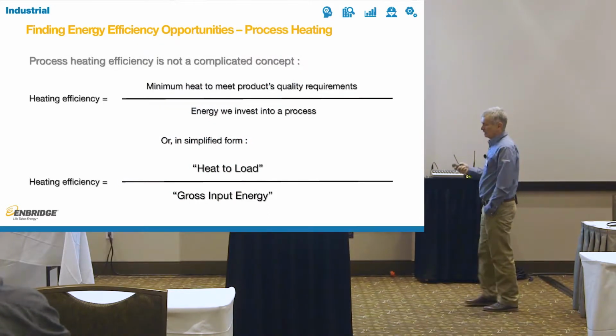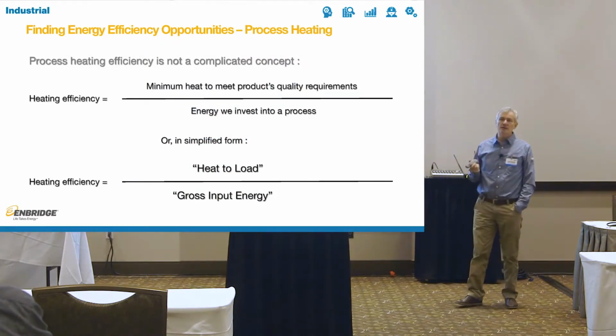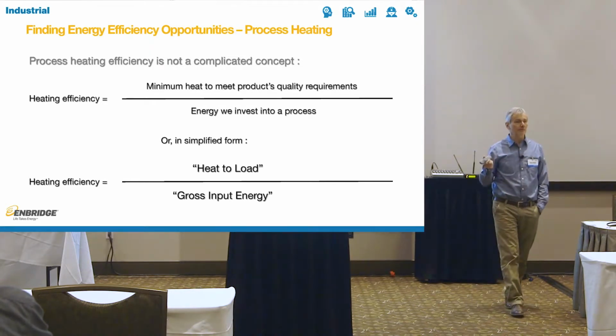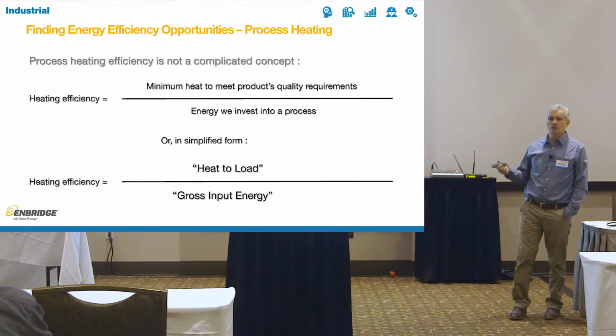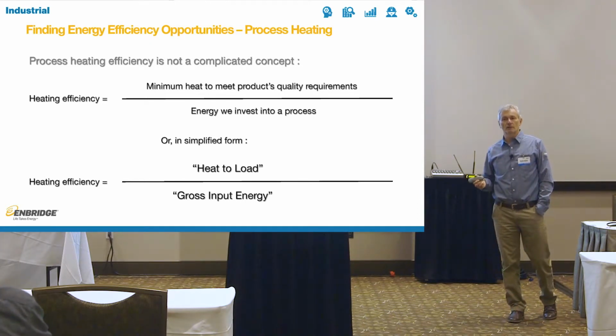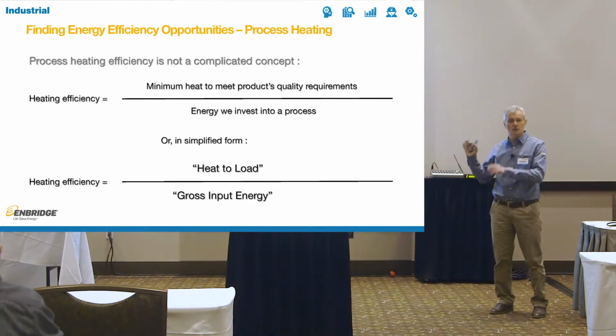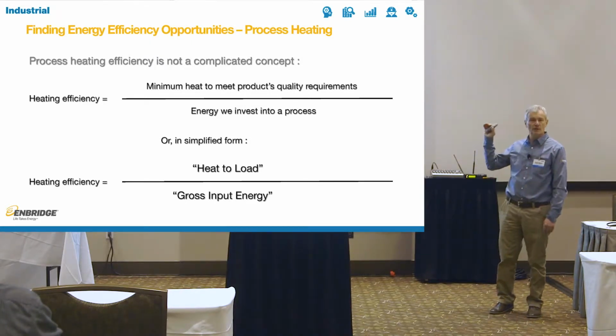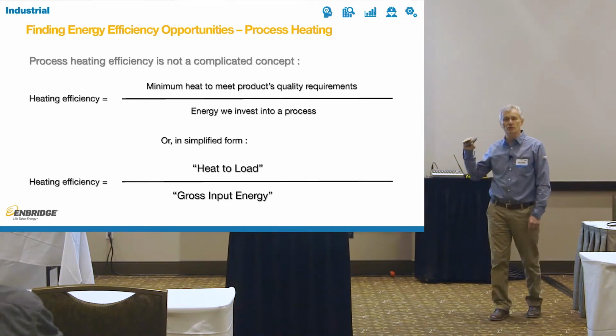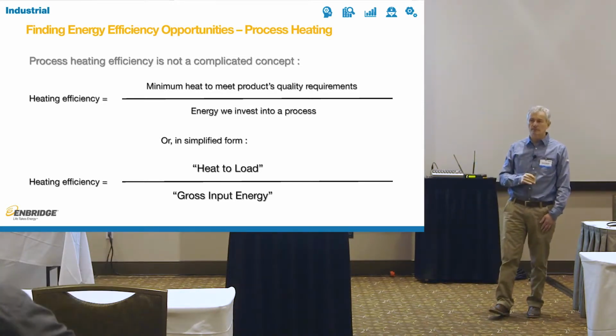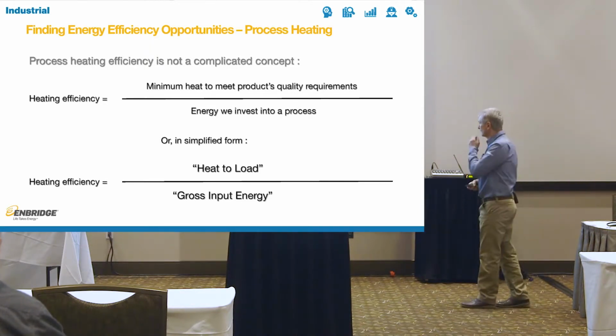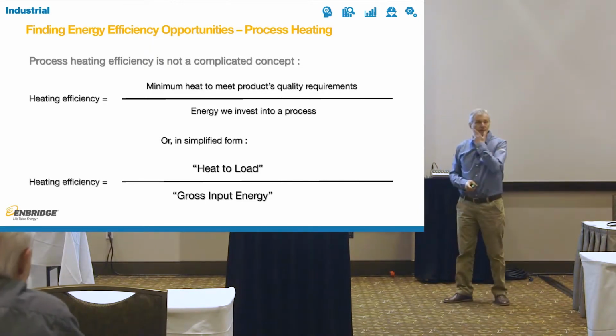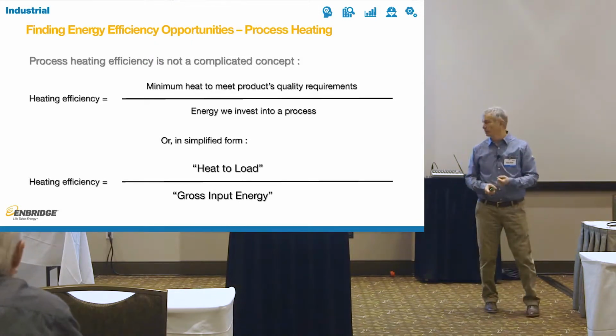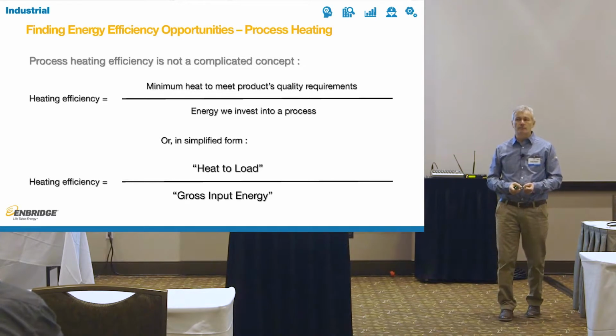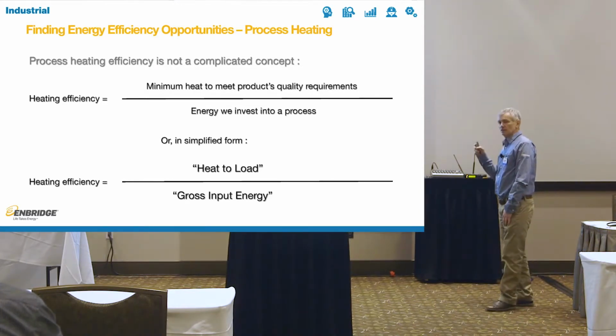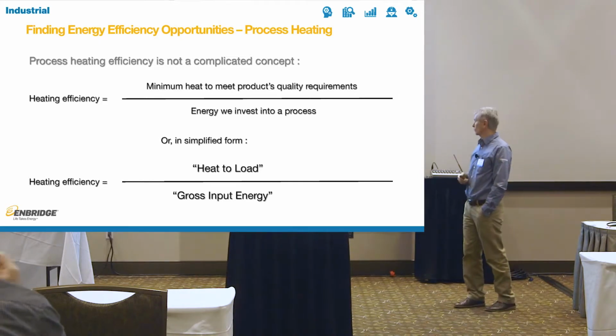So how do we define heating efficiency? It's the minimum heat to meet required quality requirements divided by the energy we invest into the process. That's the simplest way you can look at it. You can do all sorts of formulas, but essentially, how much heat you need to create your product divided by how much heat you actually pay for to put into that system. In simplified form, it's heat to load, what actually goes into your product, divided by the gross input energy. That's your heating efficiency. We'll use that terminology for the sake of this workshop.